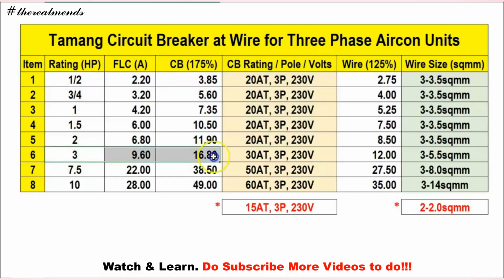So, for 3 HP, yung circuit breaker natin is 30 ampere trip. So, tatlong 5.5 square mm. For 7.5, we have 8.0 square mm. For 10 HP, we have 3-14 square mm yung kanyang wire. So, pag yung circuit breaker mo is 15 ampere trip, so yung minimum is this is tatlong 2.0 square mm. Okay, so we're done sa ating calculations ng circuit breaker at saka sa wire.